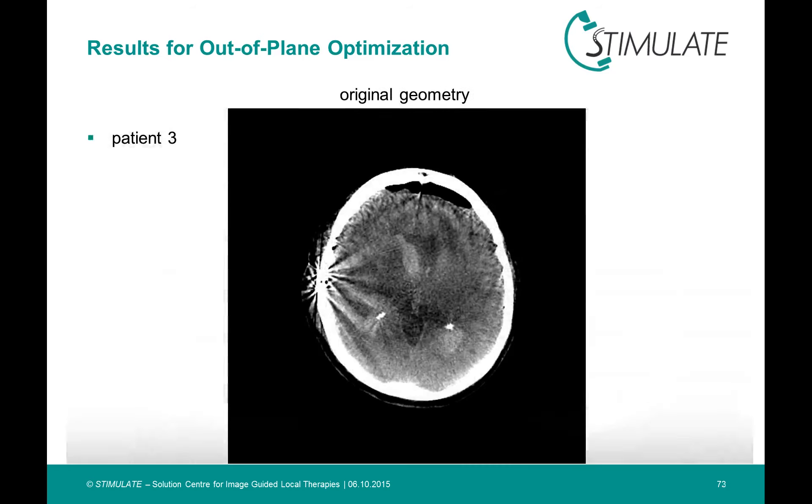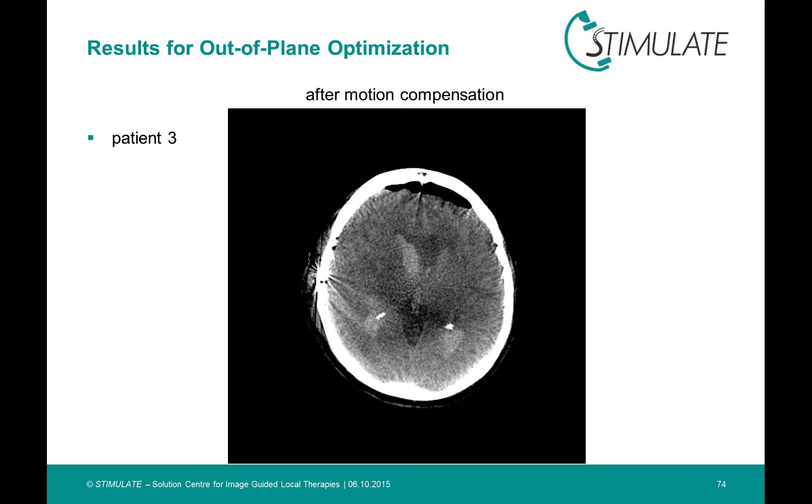Here is a further patient, where you can see also radial streaks starting at a metal plate. Also blurring at the edges of the tissue is visible. And now the same slice after the correction.